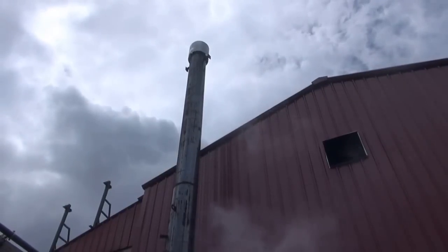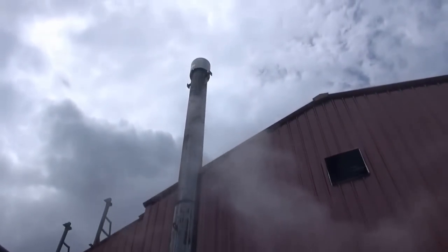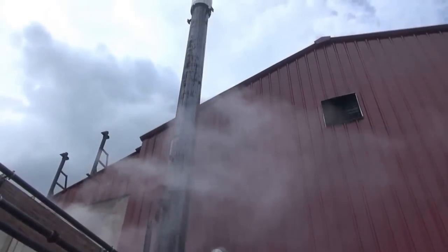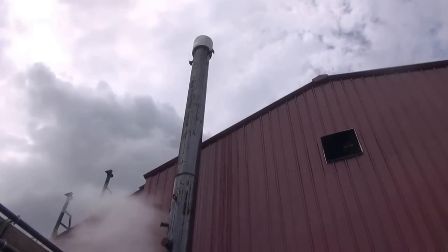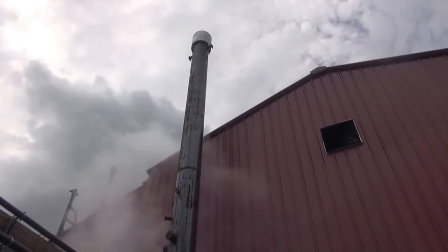The stack output is beautifully clean. The scrubber is working perfectly — we're stripping all the water out of the stack. We haven't done a full emissions series, but our preliminary testing says we've got CO of around one, so it's burning very efficiently.